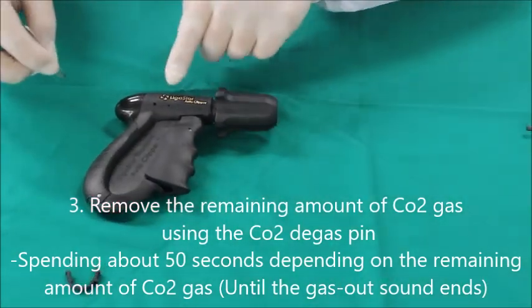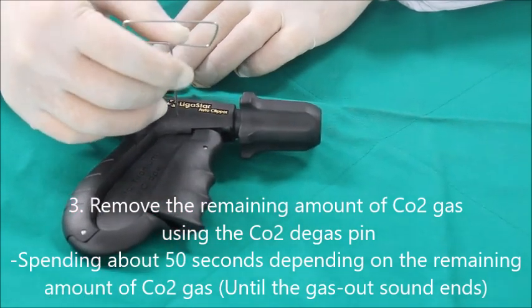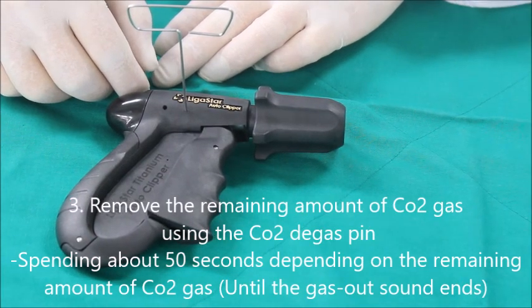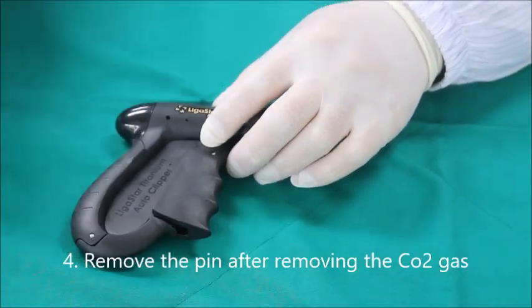remove the remaining CO2 gas using the degas pin. This may take about 50 seconds depending on the remaining amount of CO2 gas.